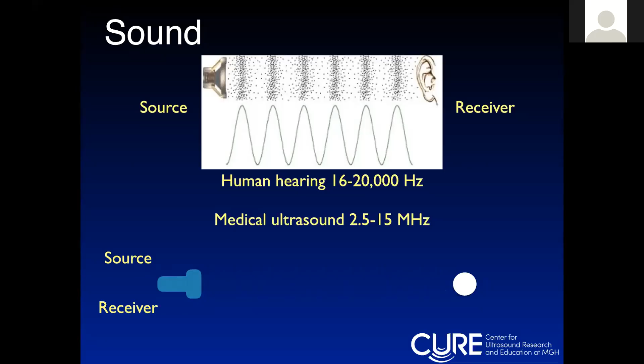Now, there's a property in the ends of probes called the piezoelectric property. There are these crystals here, and what happens is that they can transduce voltage into vibration and back and forth. So the machine sends an electric signal, voltage, the crystal vibrates, causes a sound, an ultrasound, which goes down, hits an object, and comes back. Another crystal's excited, and now it hits this object, but this object, it hit quicker, and so it came back more quickly. And so the probe translates that into depth, right?